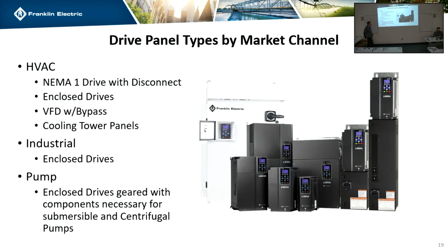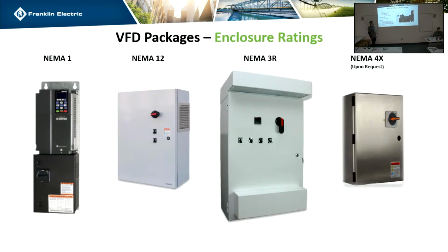Yep, and a booster would be a centrifugal package, so it's going to come with a line reactor. It's going to come sized for everything. You're going to get an HOA switch. So we can do just the drives, or the entire panel, or the panel and pumps and everything, as a skid. So we have access to... okay, here's what they all look like. NEMA 1. So NEMA 1 just means you can't stick your finger into anything that's going to shock you.